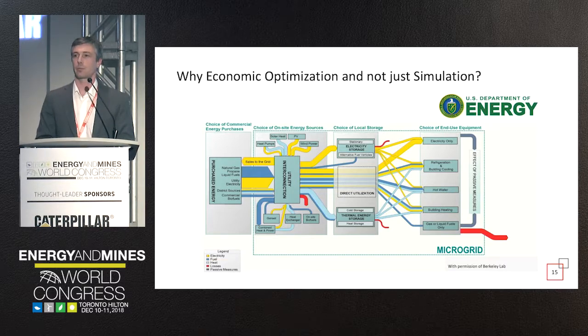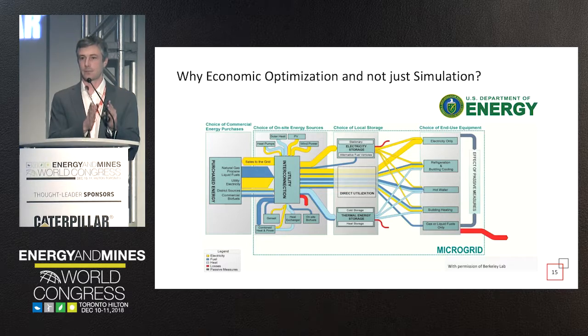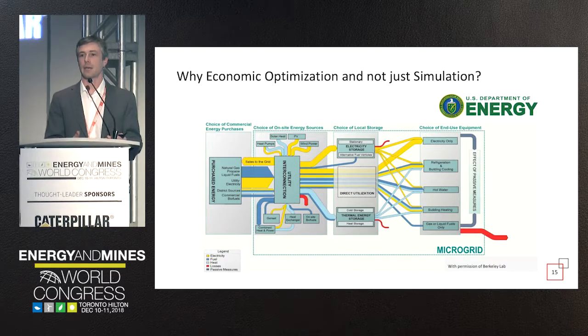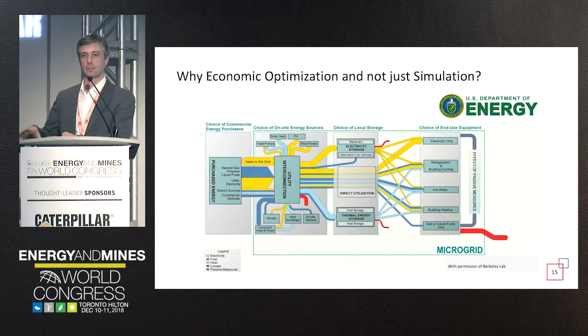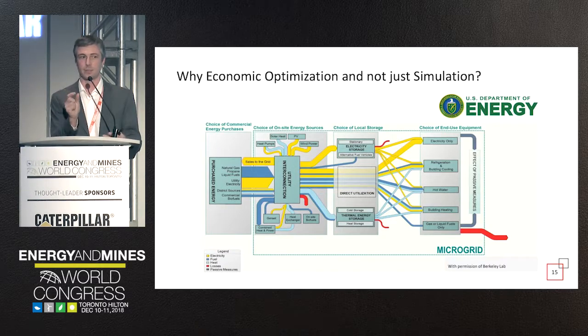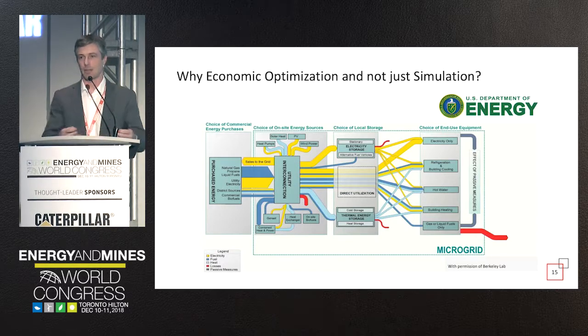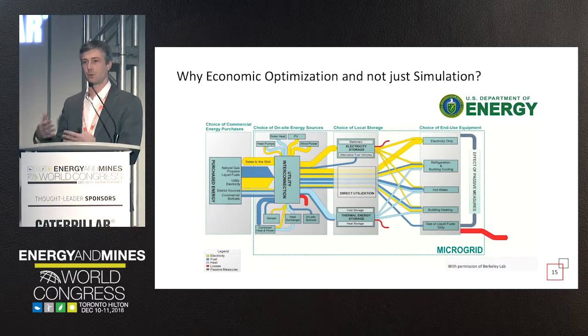To achieve that hundred percent renewable, it's very hard — the last few percent can be done, but you also have to consider, if you're being serious about environmental impact, what is the embedded energy in those systems. Getting that last four or five percent renewable may require an amount of solar generation and lithium-ion storage that — when you look at the carbon footprint of building those solar panels relative to their value in displacing diesel for that last little percent — creates competing priorities that are very hard to conceptualize, let alone accurately account for in an optimization process.